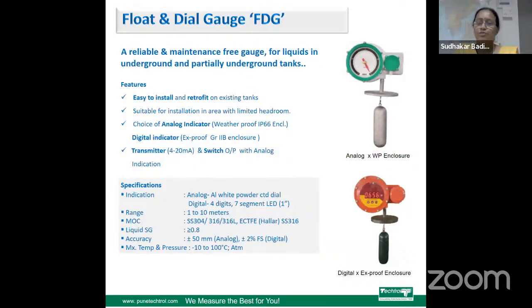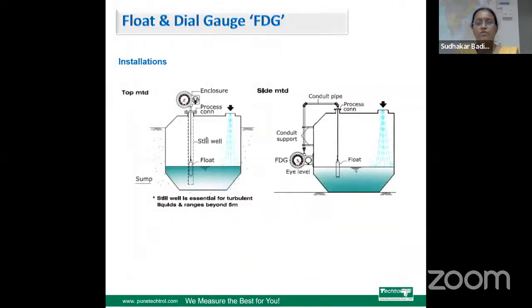The range of this instrument is up to 10 meters. The material is available in stainless steel, then ECTFE coated stainless steel. It is suitable for a maximum temperature of 100 degrees Celsius and atmospheric pressure. The gauge can be mounted on the top of the tank. On the left side, you can see the gauge mounted on the top of an underground tank. And on the right side, you can see the gauge mounted on the side of the tank, which is an above ground tank. Here the indicator is mounted at eye level from the ground.